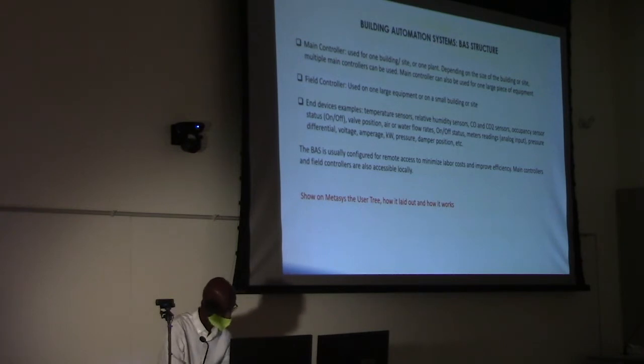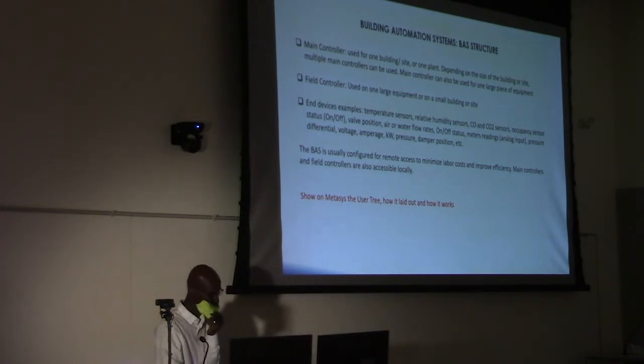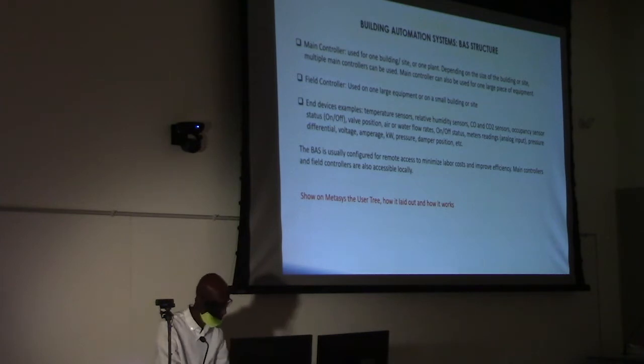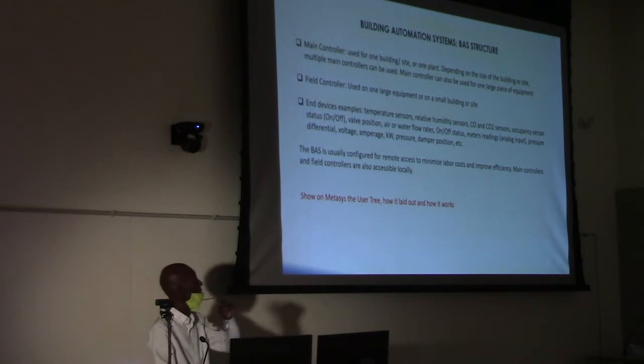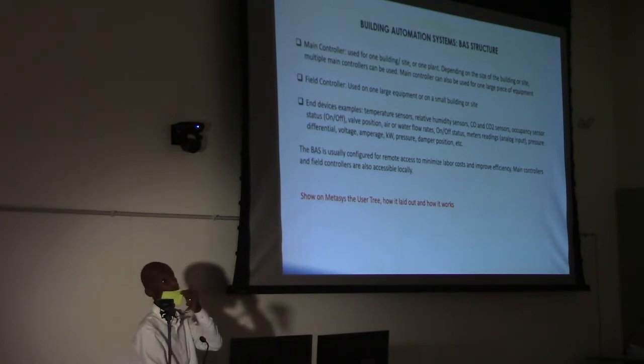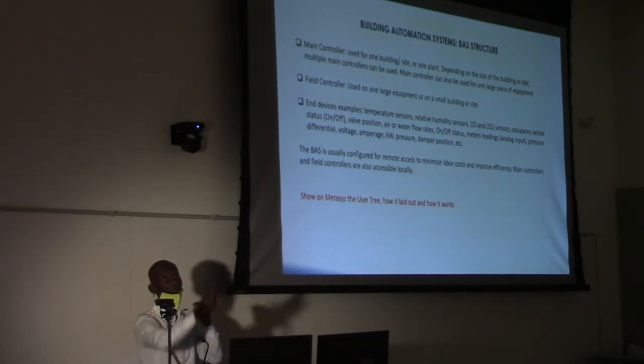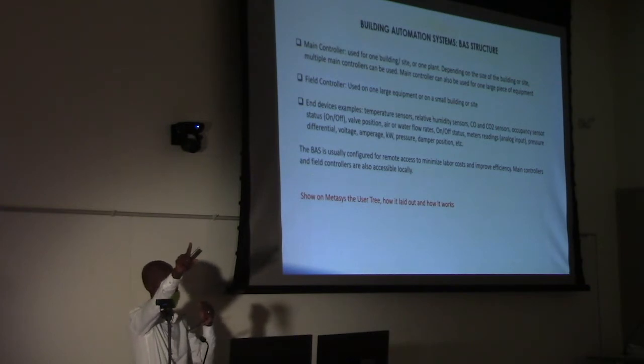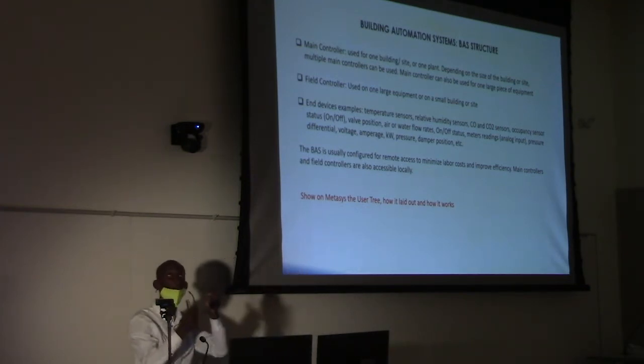Field controllers are used on one large equipment or on a small building or site. And the devices examples are temperature sensor, relative humidity sensors, CO and CO2 sensors, occupancy sensors. We may have some here, probably. Yeah. Yeah, over there I can see one. That may be another one.